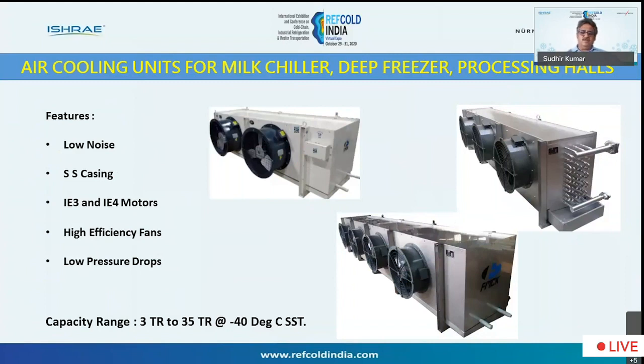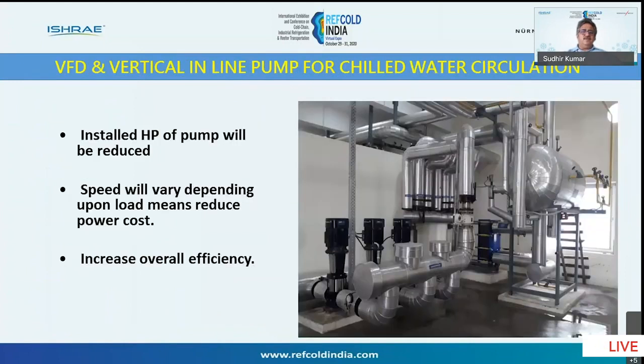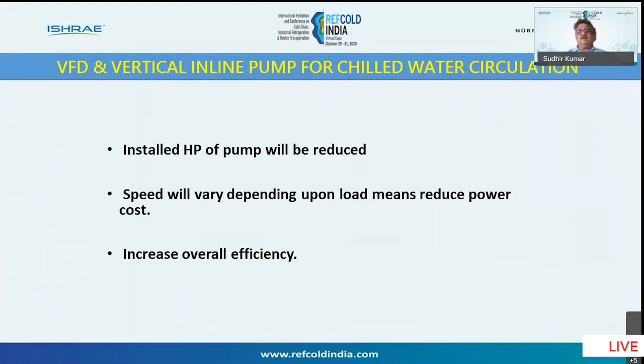And this also gives you a lot of saving by using IE3 and IE4 motors. And after finishing off with the refrigeration system, you come into the chilled water side. Once you come to the chilled water side, you can use the energy efficient vertical inline pumps. Again, these are directly coupled pumps, and these have a reduced horsepower as compared to the normal pumps. And also similarly, based on your load requirement, you can have a variable frequency drive even in the chilled water circuit, and by that you can manage your refrigeration system capacity also.